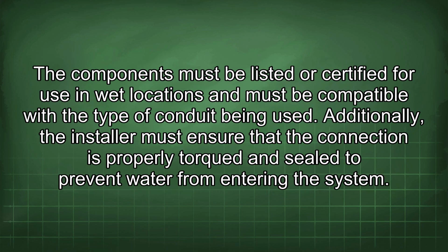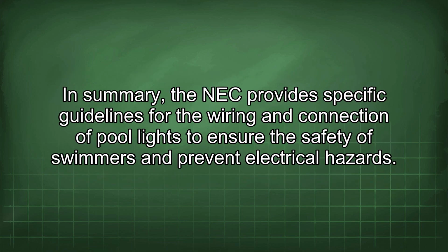The components must be listed or certified for use in wet locations and must be compatible with the type of conduit being used. Additionally, the installer must ensure that the connection is properly torqued and sealed to prevent water from entering the system. In summary, the NEC provides specific guidelines for the wiring and connection of pool lights to ensure the safety of swimmers and prevent electrical hazards.